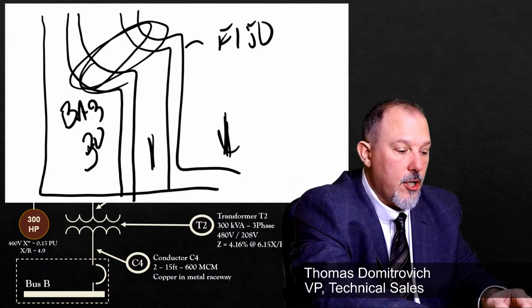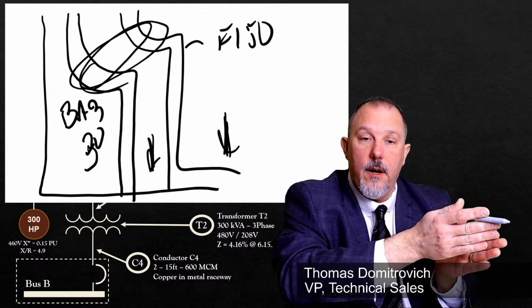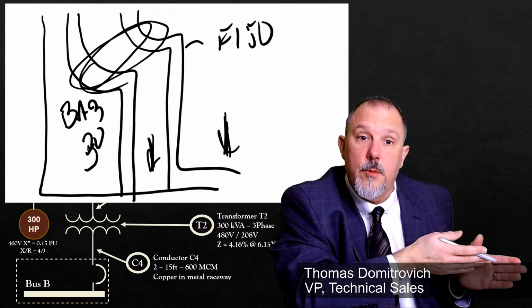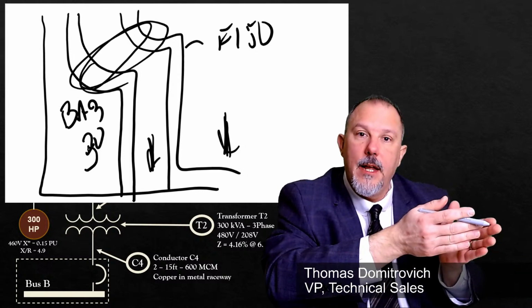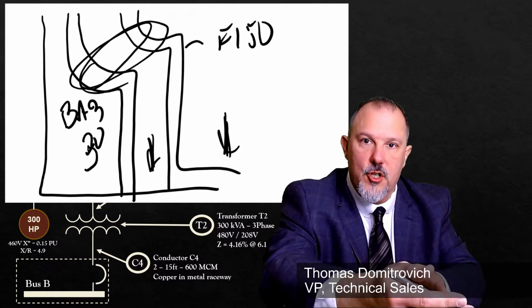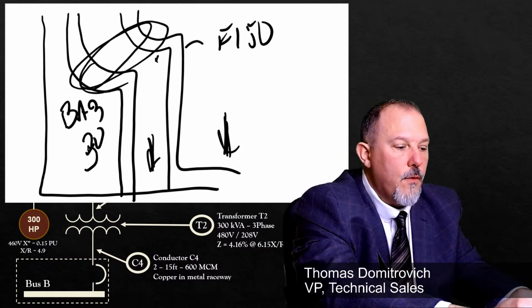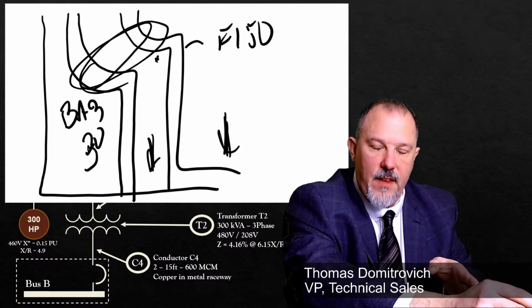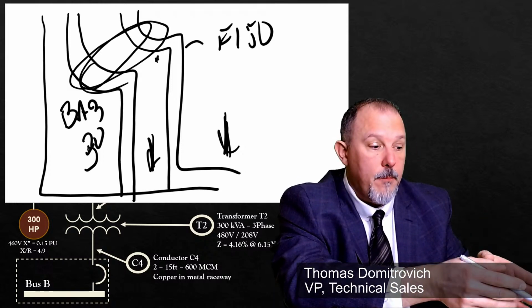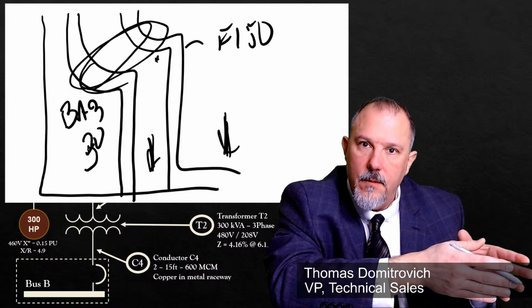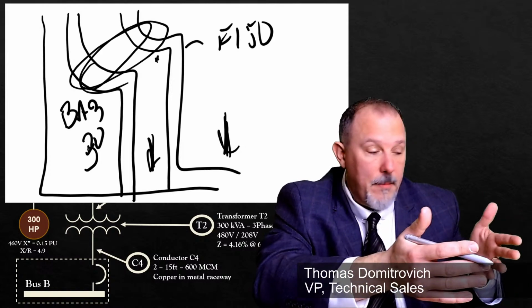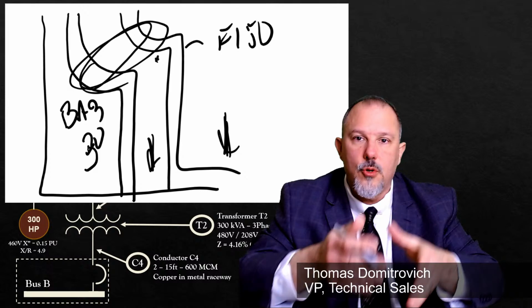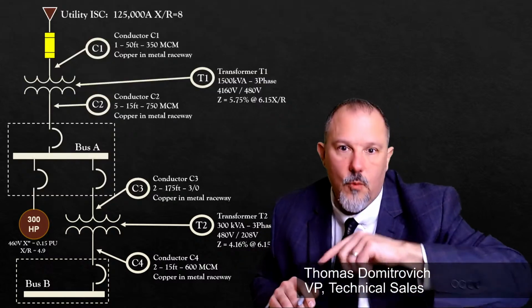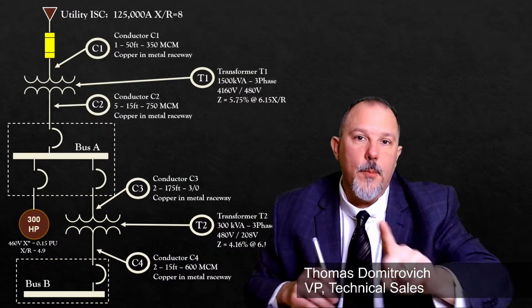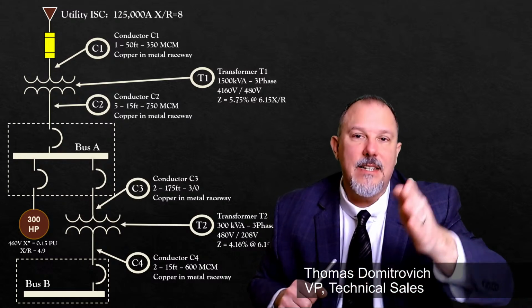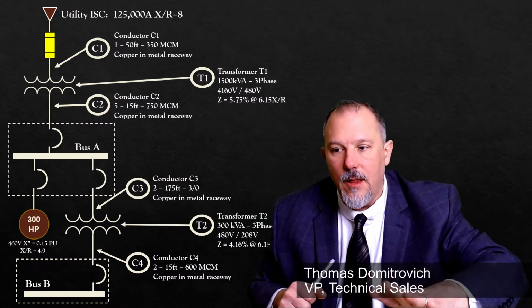You could have a short circuit current that's low enough from an upstream source. It might be in the instantaneous region of this downstream breaker, but not in the instantaneous region of the upstream breaker. So you're in the overload region on this F150 for this short circuit current, but it's not an overload. Does that make sense? I hope it makes sense. So we say from overload to short circuit because in the definition, we are more concerned about helping you understand what current you need to selectively coordinate to. And that's where a lot of debate occurs.